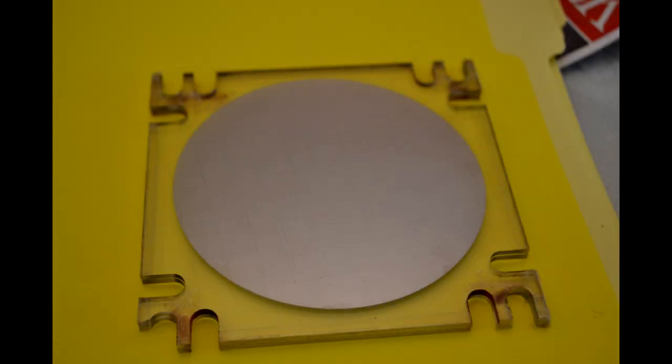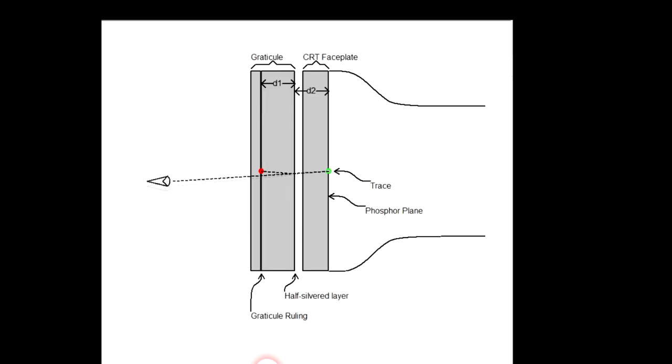The layer closest to the CRT faceplate is a half-silvered mirror which reflects some light and lets the remainder pass through. A viewer looking through the assembly sees the trace on the phosphor layer as well as a reflection or virtual image of the graticule grooves.